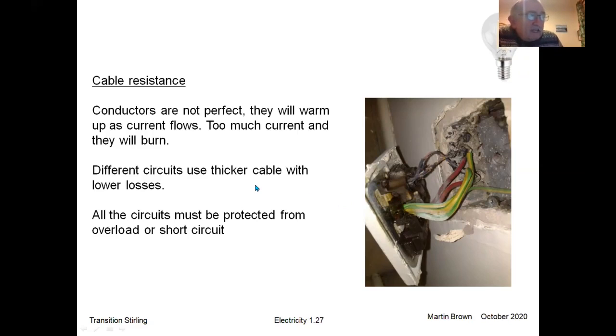It's also complicated because different circuits use thicker or thinner cables. If you've got a lighting circuit, you don't need to have a thick cable. If you've got a cooker or a shower, you do need a thick cable. So different cables, different load capabilities and different overload capabilities. And they must all be protected from overload or short circuit. So how do we do that?